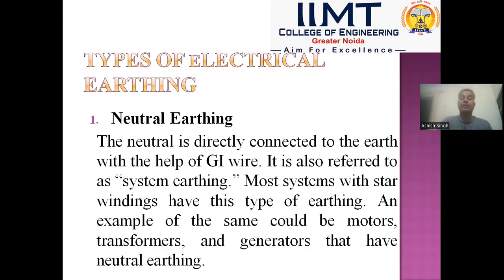star connected transformers, three-phase motors, generators, and transmission lines are earthed with the help of neutral earthing. In this case, a neutral terminal is connected to the earth with the help of a short piece of wire. So most systems with star winding have this type of earthing. Examples could be motors, transformers, and generators that have neutral earthing.